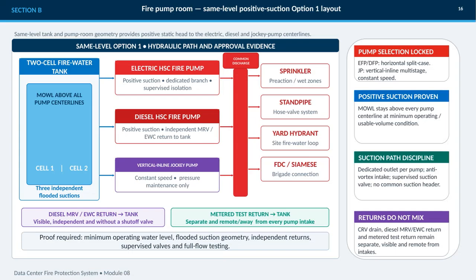This slide presents the same level, positive suction option 1 layout for the fire pump room. The two-cell fire water tank and pump room share the same elevation, so the minimum operating water level remains above every pump centerline. That is the basis for positive static head, and it must be proven under the usable volume condition. The suction arrangement is deliberately independent. Each pump has its own dedicated, flooded branch, anti-vortex intake, and supervised isolation valve, with no common suction header. The electric and diesel pumps use horizontal split-case configurations, while the jockey pump is a constant speed, vertical inline multistage unit used only for pressure maintenance.